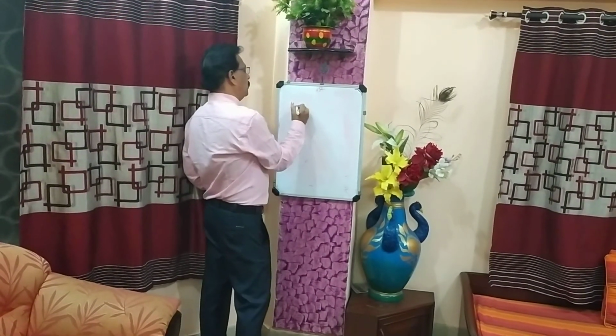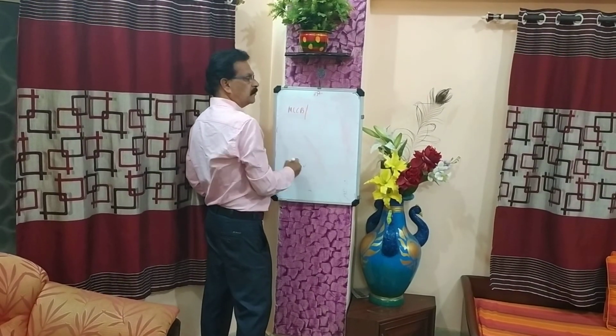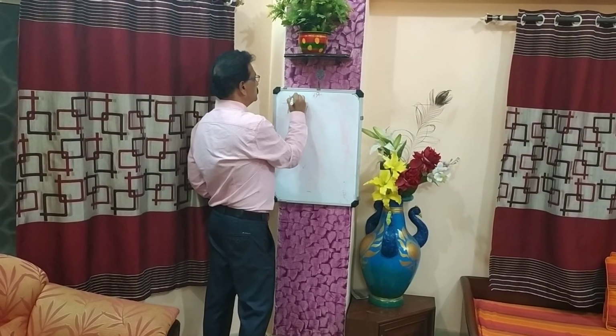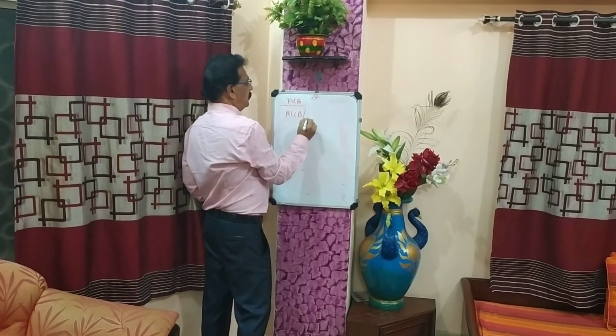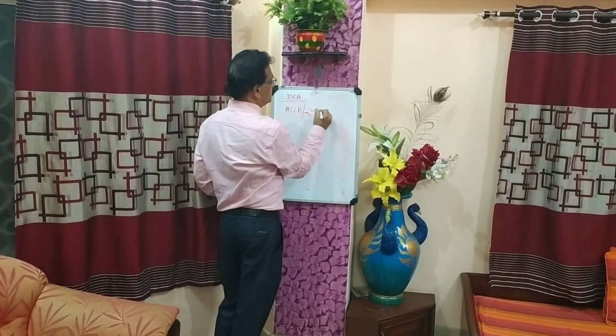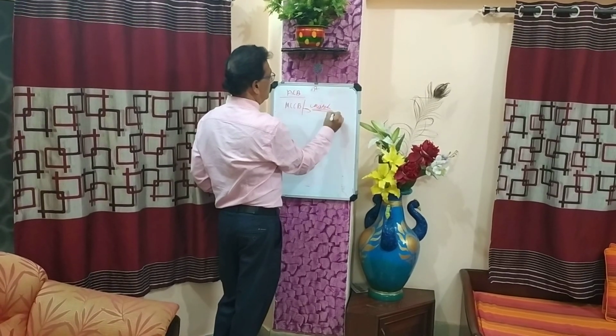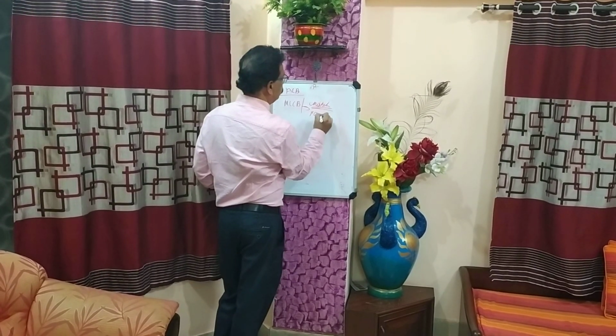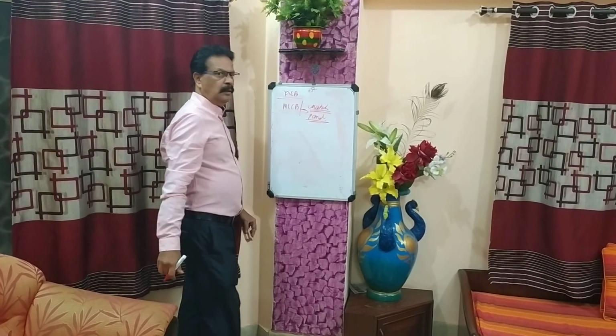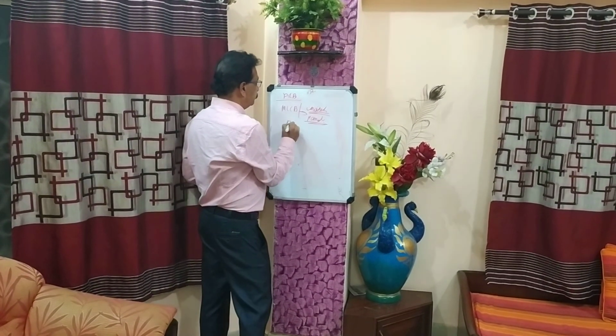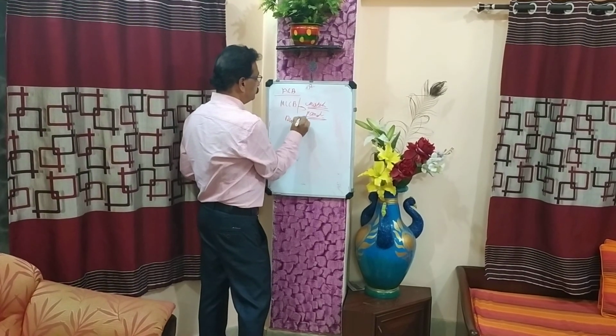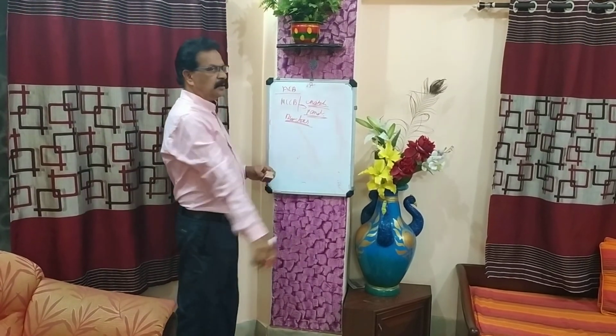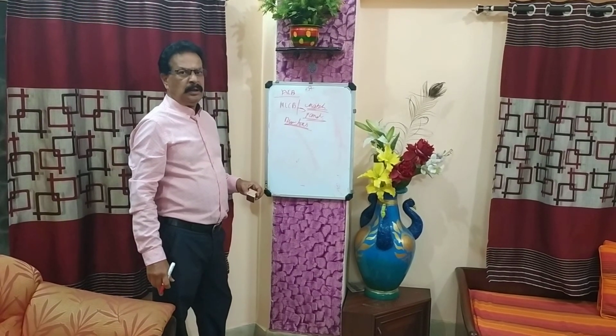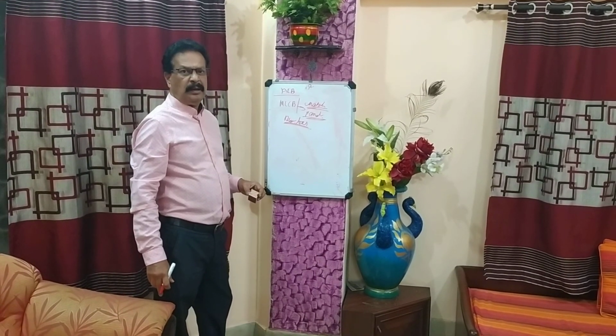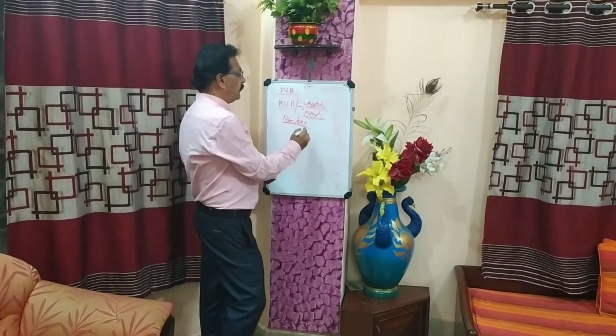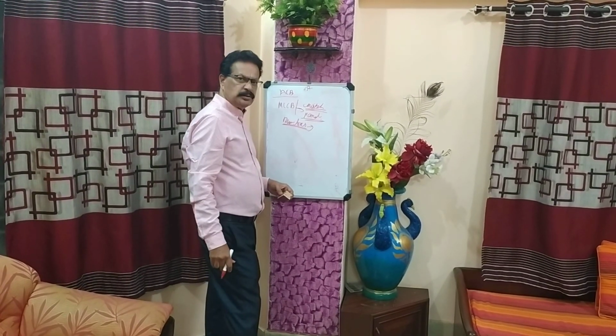Use the MCCB, and for upper size, ACB. After MCCB come the switches, panel mounted switches. The bus bar should be copper. Measure the load, measure the calculation, check how much ampere it's going to pick up. The main thing is how much load you are going to get. With that, you find out what size bus bar you have to use.